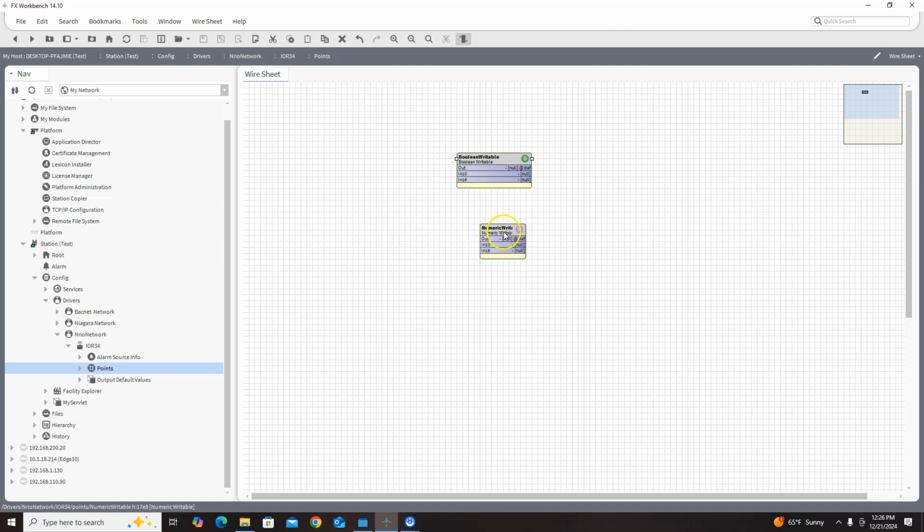The next one we got is a numeric. So a numeric is any number, positive or negative. Okay. So this is where we slowly open a valve, right? We give it 10% open, 20% open, 30% open. Okay. We can do that with valves. We can ramp up fans to give more pressure, more air, more CFM going through an air handler by giving a VFD a signal, right? That's going to be a numeric point.